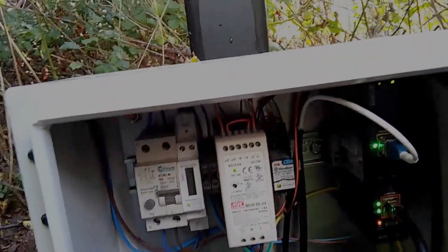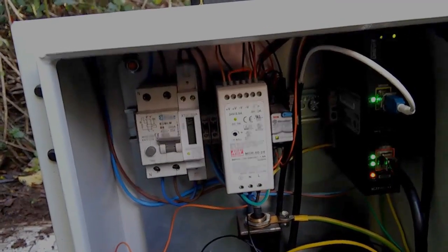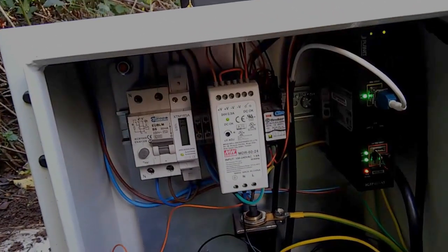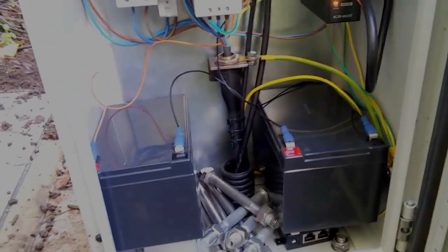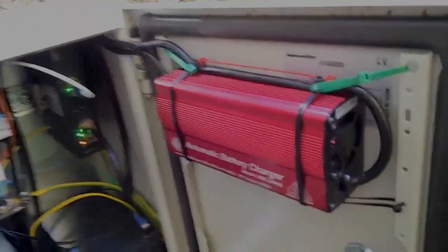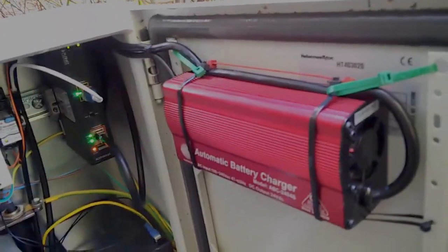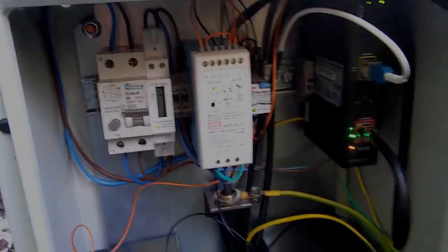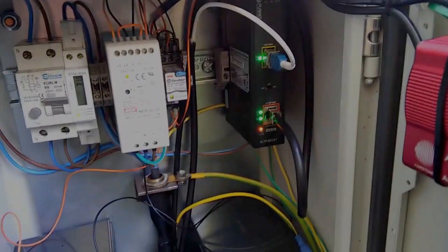Also, this relay here, whilst the power supply is on, switches these two batteries - a pair of 12 volts wired so that they're 24 volts. It switches those over to this battery charger here, which is also fed by the main supply. So when the main supply is on and the 24 volt power supply is working, this charger charges the batteries, and this power supply powers the media converter.